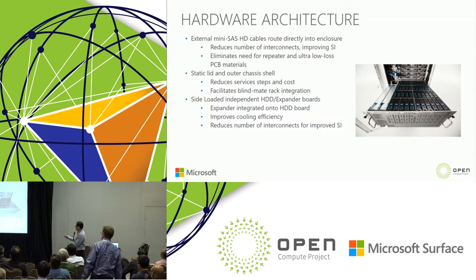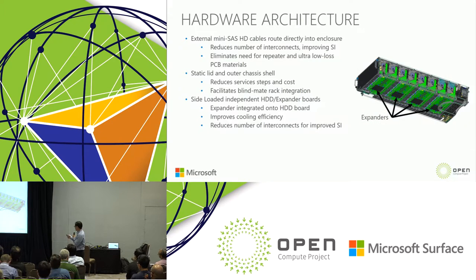The third feature is a side-loaded, independent HDD/Expander board. We put the expander onto the backplane board, which leaves maximum space for the heat sink design, resulting in better thermal cooling and higher thermal efficiency. Putting the chip on board also reduces interconnectors and improves signal integrity. These three key implementations deliver better signal integrity, serviceability, thermal performance, and cost savings.